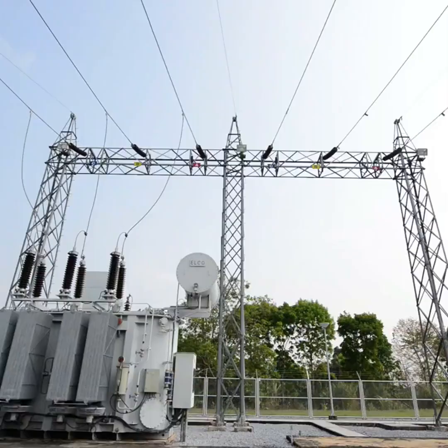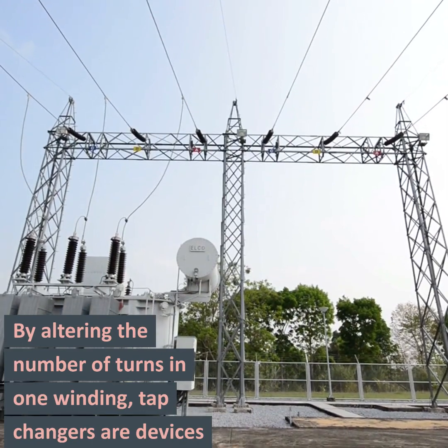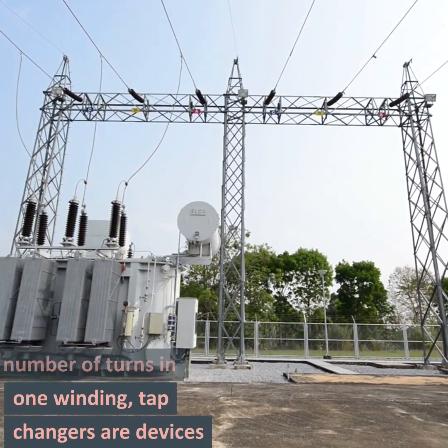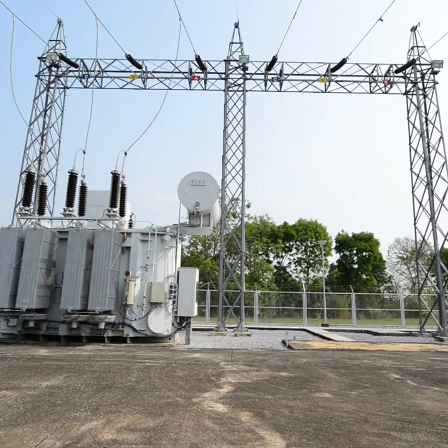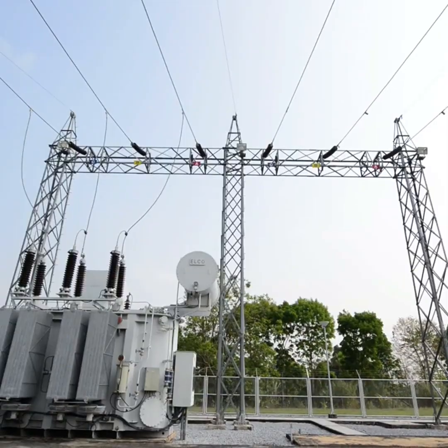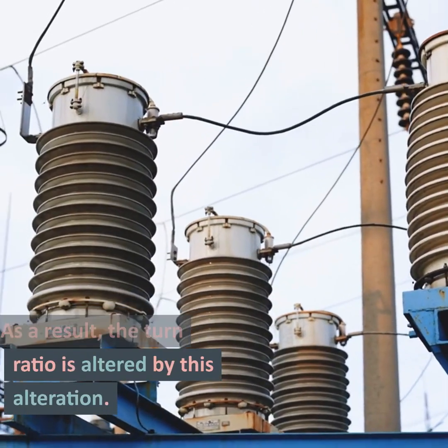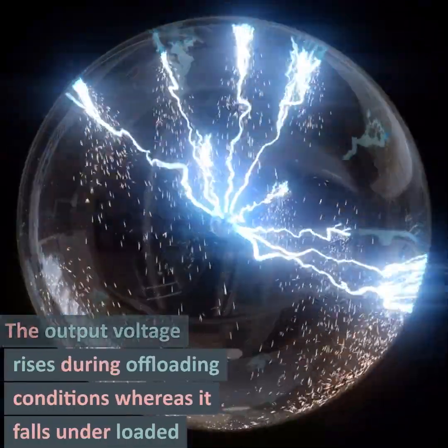Tap changer. By altering the number of turns in one winding, tap changers are devices that control the transformer's output voltage as it responds to the varying input voltage and load. As a result, the turn ratio is altered by this alteration. The output voltage rises during off-loading conditions whereas it falls under loaded conditions.